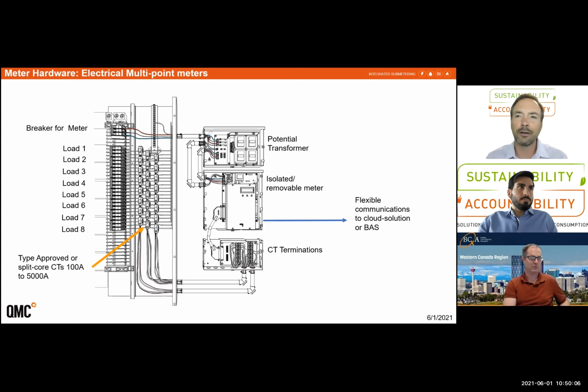We find a lot of buildings these days are moving toward metering everything. And as much as that's great for the metering industry, sometimes it's metering overkill, where they're metering every circuit. And before even entire floors are metered or other utilities are metered properly, like you're missing the entire water irrigation system, but you're metering toaster loads, right? We really believe in that balance of metering large loads first before you get down to metering individual plug loads or individual lighting circuits, as an example.